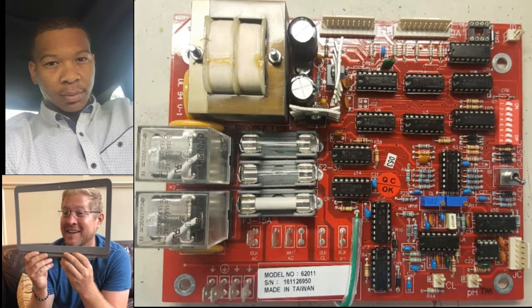Right. And then we move from there to the fuses. Now, are the fuses upstream of the relay or downstream of the relay? Are the fuses for the ORP and pH before or after the relay? The fuses, I believe they're before the relay. So if you didn't hear the relay clicking on and off, it could be the fuse, because the fuse is before the relay. No, I correct that. It was still activated. The relay was still activated.